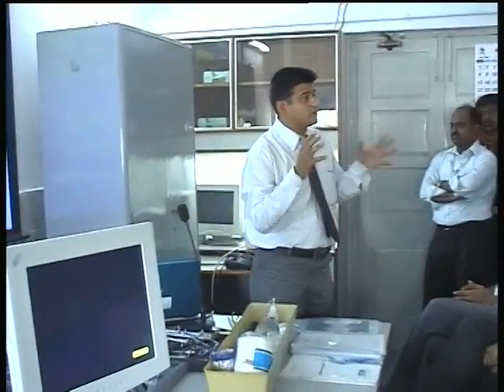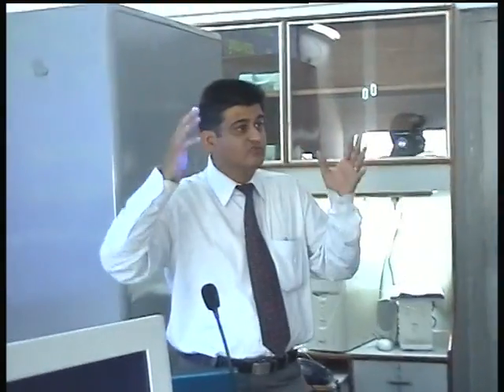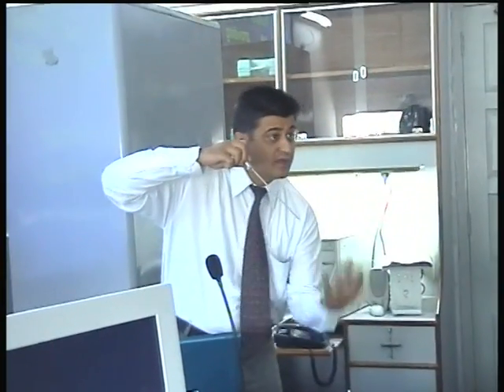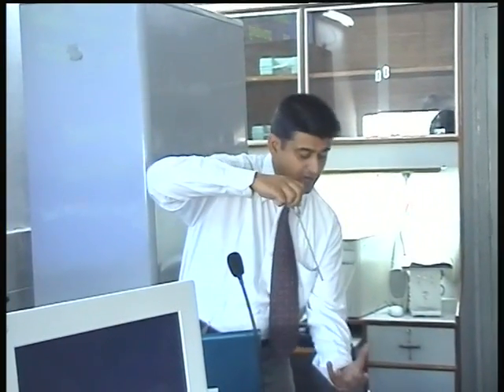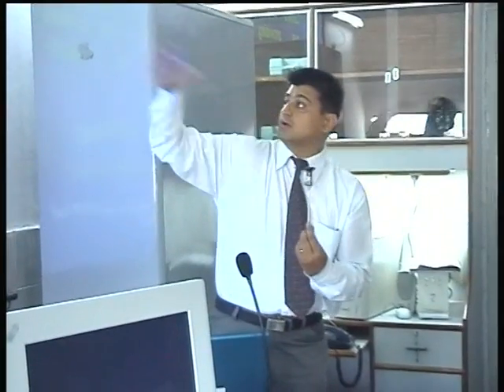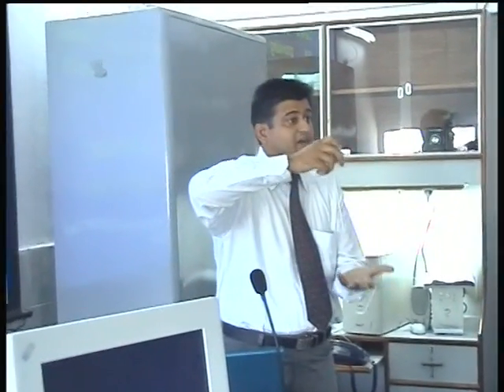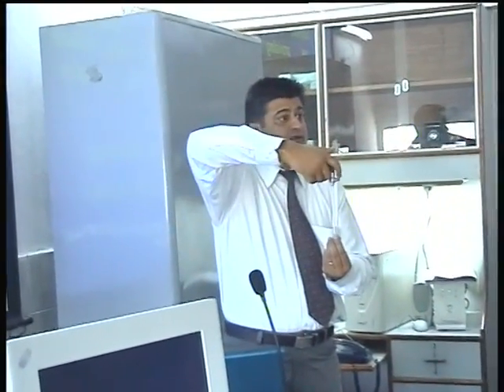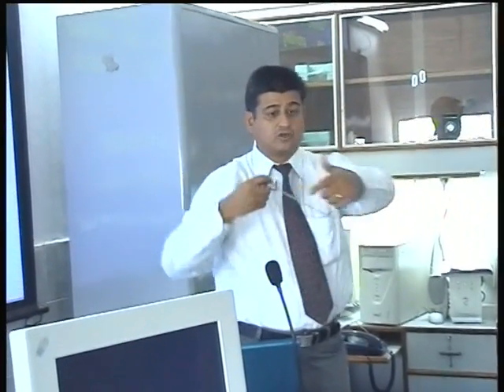There are times when we have walked into the operation theatre and not found the vision as it should be, and we have redone the white balancing again. White balancing is very important. How it is done, once the camera is connected, you keep an absolutely white gauze piece down. The whole endovision circle should be covered with the white background, and then you press the white button for the white balancing.